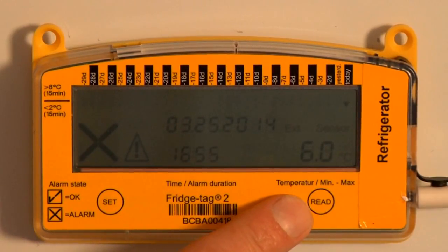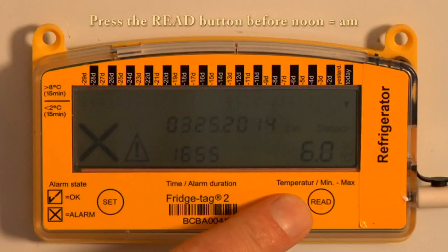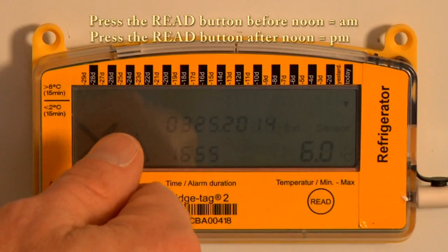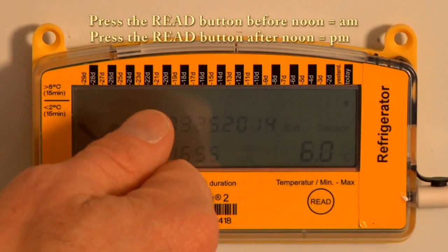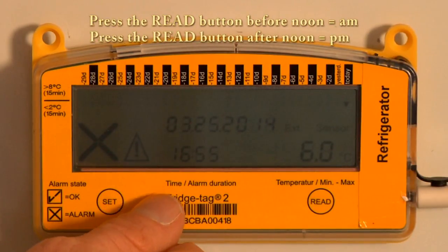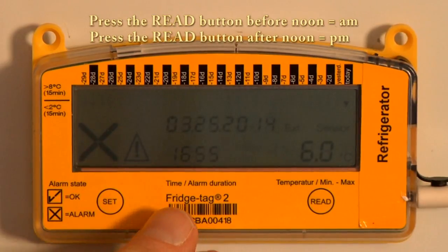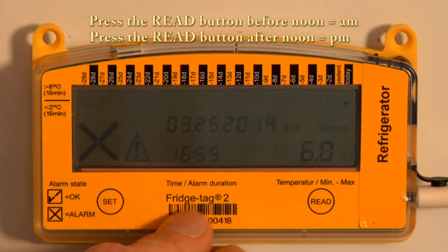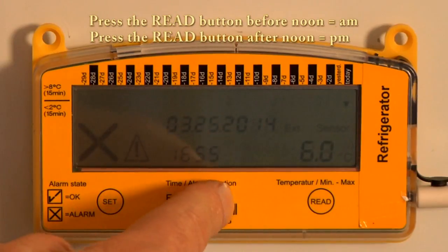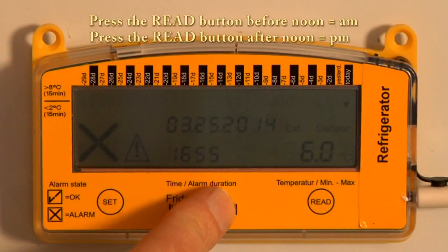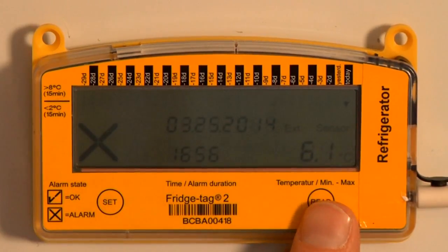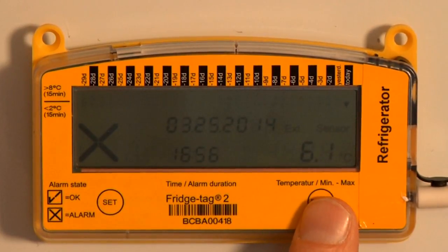If the read button is pressed before noon, it will record an A.M. in the events column of the report. If pressed in the afternoon, it will print a P.M. in the events column. Each day, the office staff should have both an A.M. and P.M. observation to ensure that temperatures are properly tracked. Press the read button one more time to clear through today's readings.